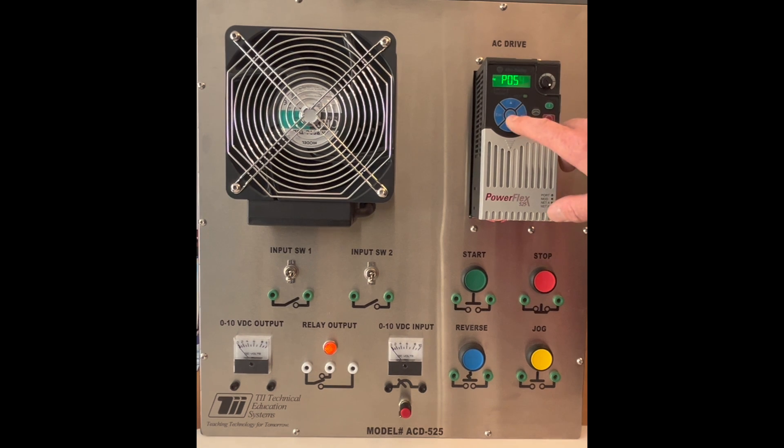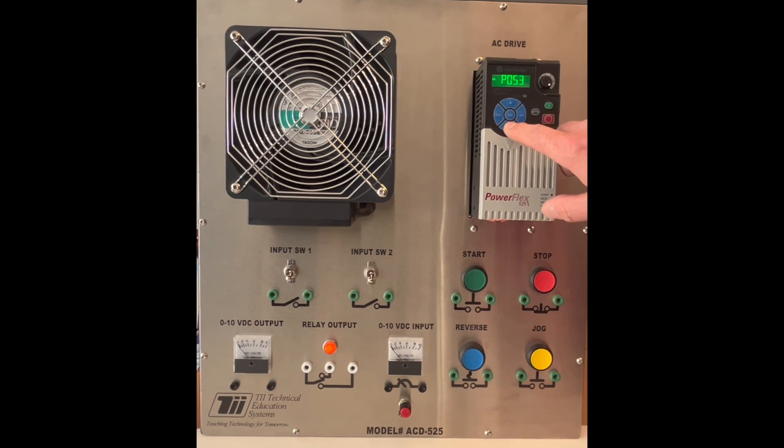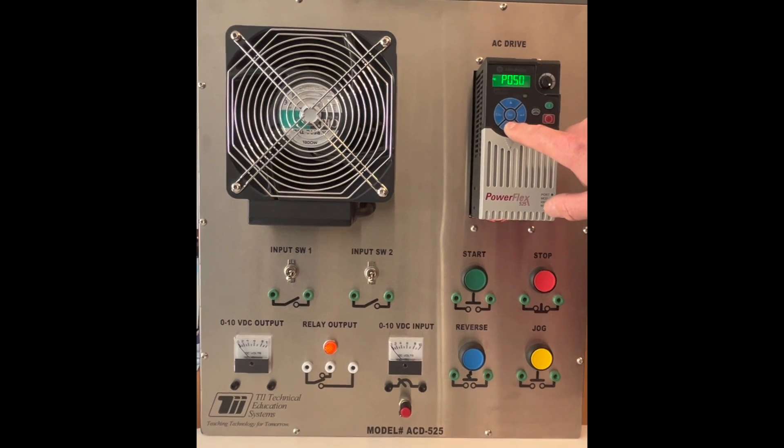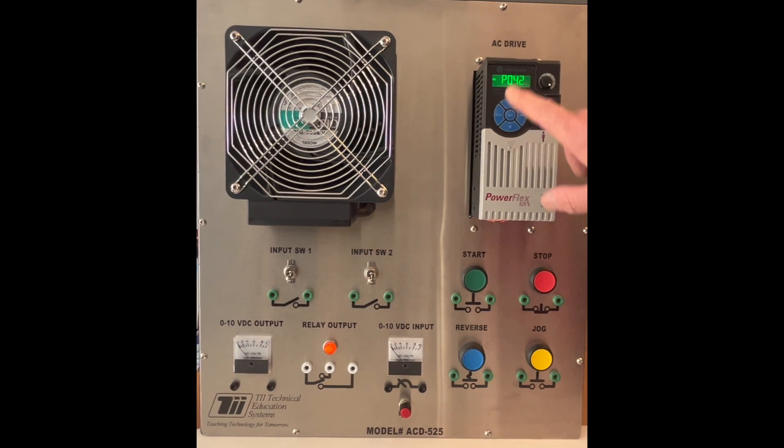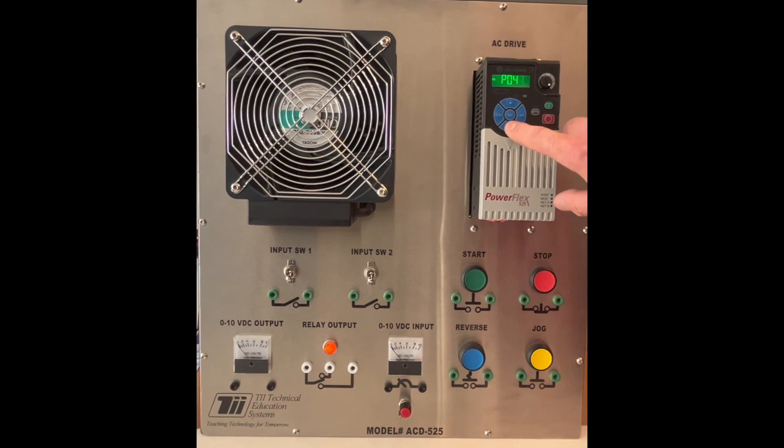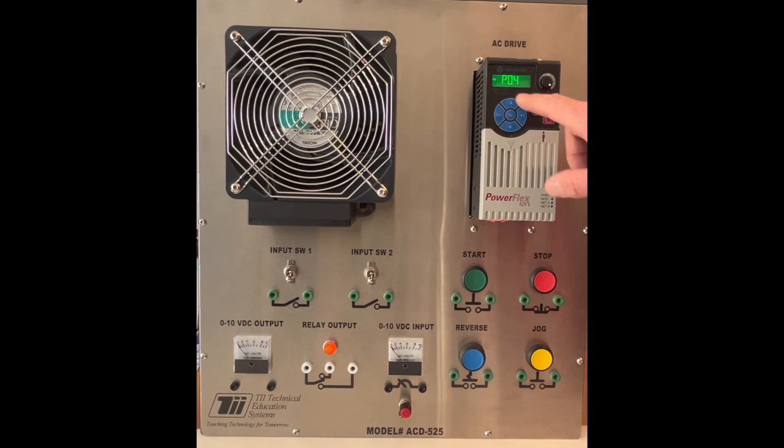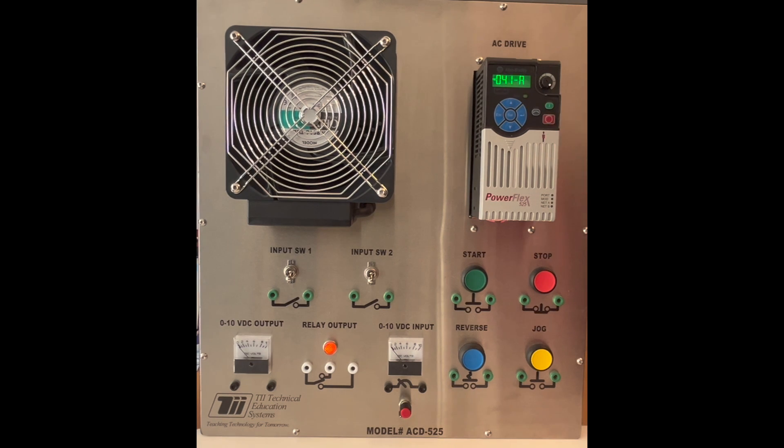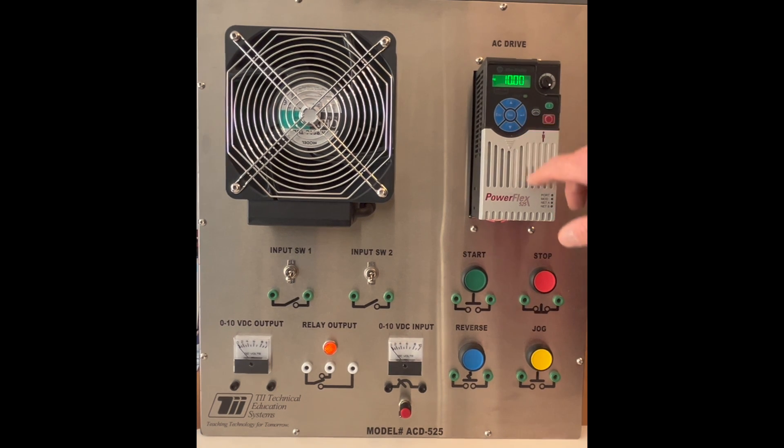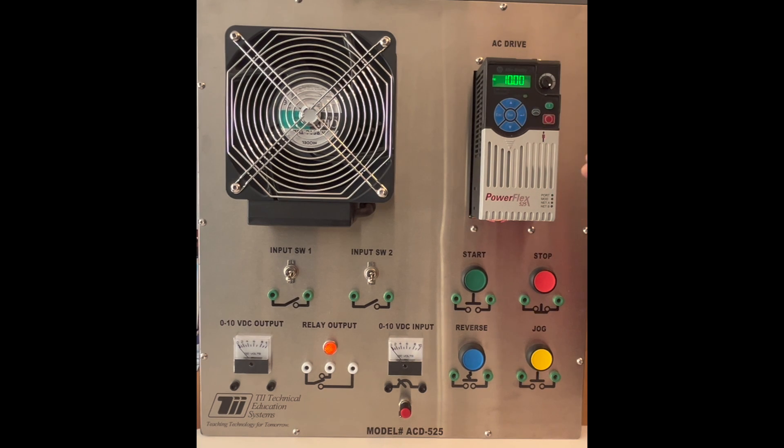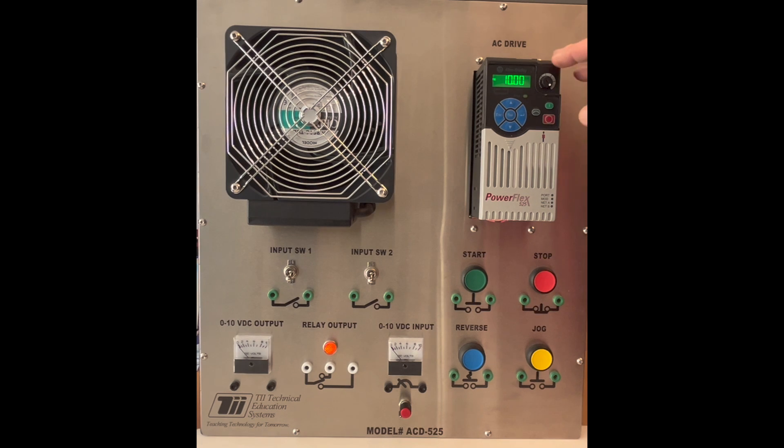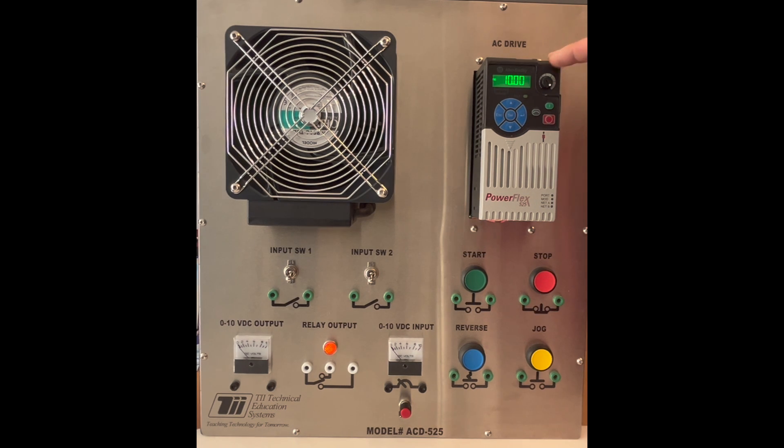So we'll select this and then we're going to go down and we'll do the acceleration time first. So we'll come here so P41 is the acceleration time so we'll hit the enter key and you'll see in the factory settings it comes as 10 seconds. That means the VFD will take 10 seconds to ramp up to whatever the frequency is set to. In this case it's set to 60 Hertz.